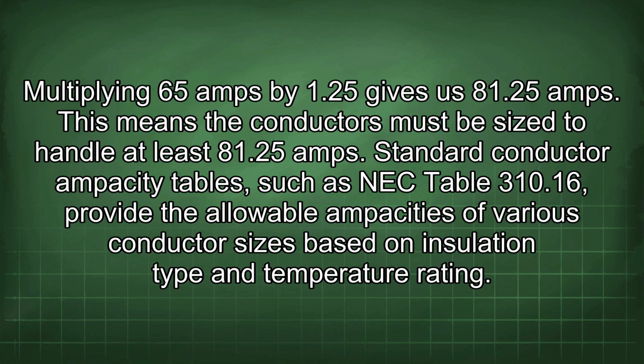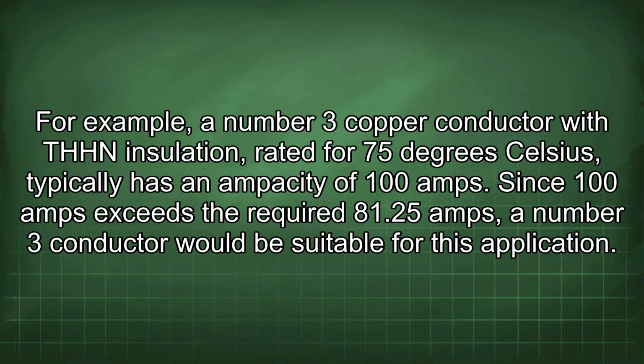Standard conductor ampacity tables, such as NEC table 310.16, provide the allowable ampacities of various conductor sizes based on insulation type and temperature rating. For example, a number 3 copper conductor with THHN insulation, rated for 75 degrees Celsius, typically has an ampacity of 100 amps. Since 100 amps exceeds the required 81.25 amps, a number 3 conductor would be suitable for this application.